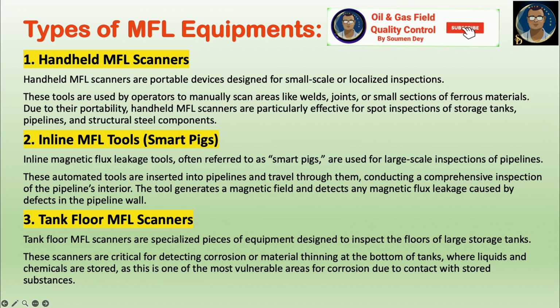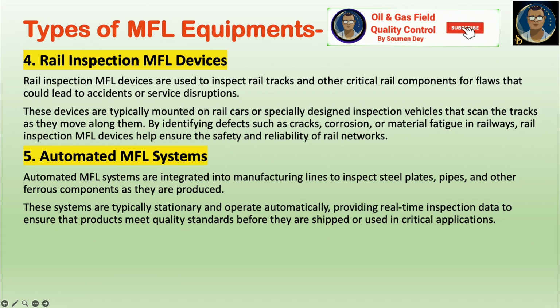Okay, tank floor MFL scanners. The tank floor scanners are specialized pieces of equipment designed to inspect the floor, especially for large storage tanks. These scanners are critical for detecting corrosion or material thinning at the bottom of the tank where liquids and chemicals are stored, and this is one of the most vulnerable areas for corrosion due to contact with the stored substances.